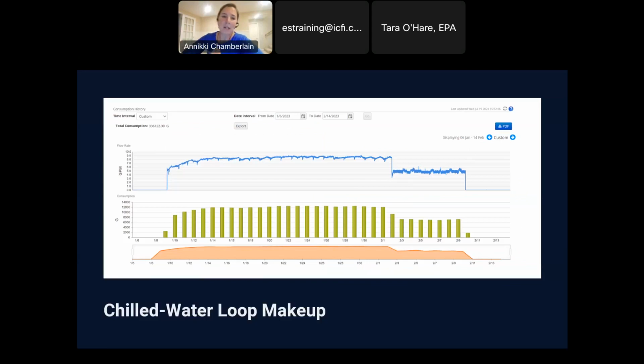Okay, here's a good one. So this one, again, was a hospital. This is on the chilled water line. So this means it's a closed loop water line that's going through the building, picking up heat and exchanging that heat in the chiller to give it to the cooling tower. So right away, what do I see that's wrong? Again, we have our gallons per minute, and this is day down here. On a chilled water line, you should actually never have water flow, maybe a tiny bit of makeup. So in this amount of time, all of a sudden there was really big flow, basically 20,000 gallons a day.